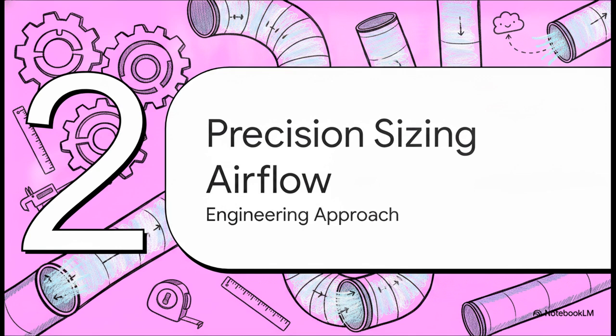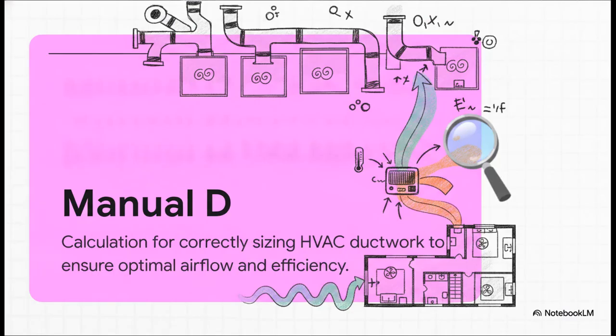Moving right along to Section 2, Precision sizing and airflow. So the crucial point is how we actually determine the size of the ducts. We never just guess. We use Manual D. By definition, Manual D is the industry standard mathematical calculation for correctly sizing HVAC ductwork. It ensures optimal airflow and efficiency. We calculate the precise load and airflow requirements for every single room in the house. That means you never have to deal with an uncomfortably warm master bedroom or a freezing cold guest room ever again.